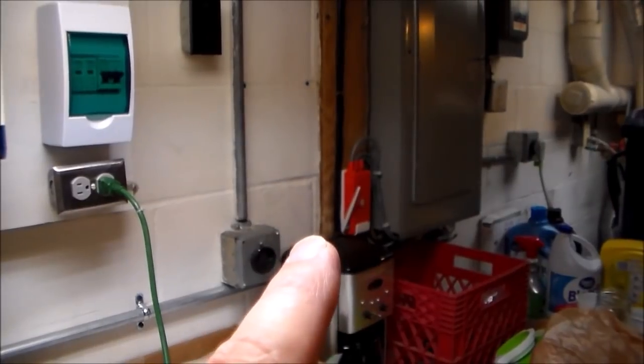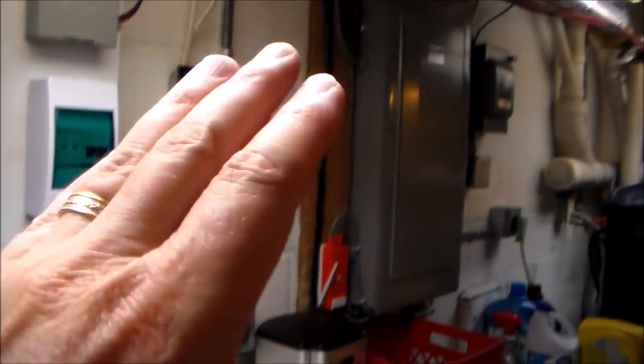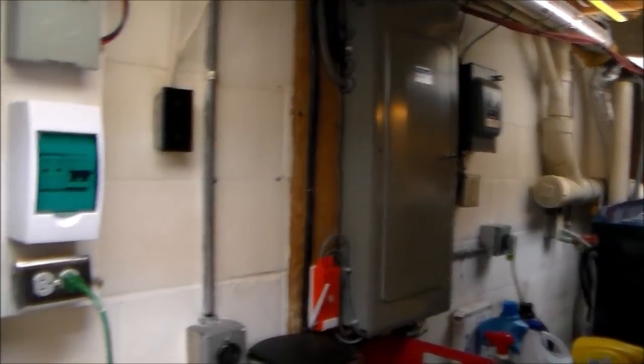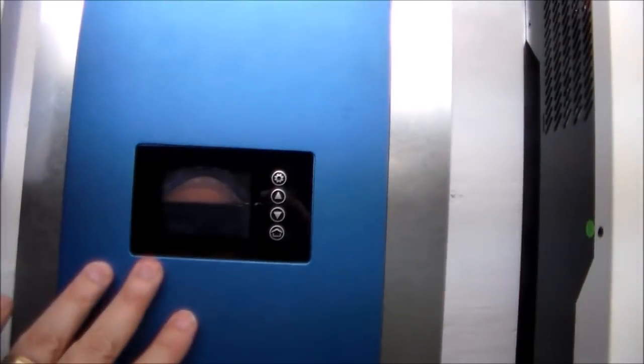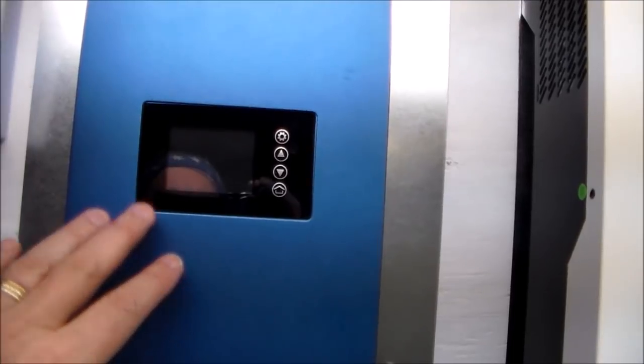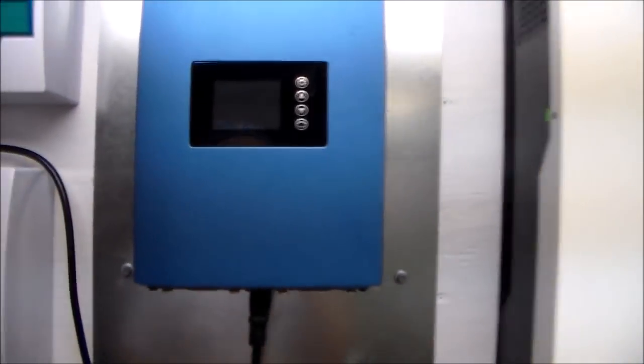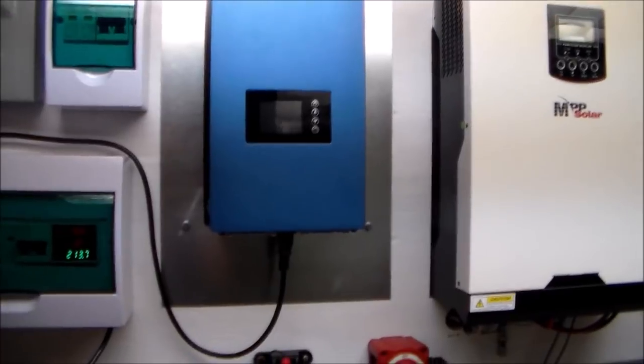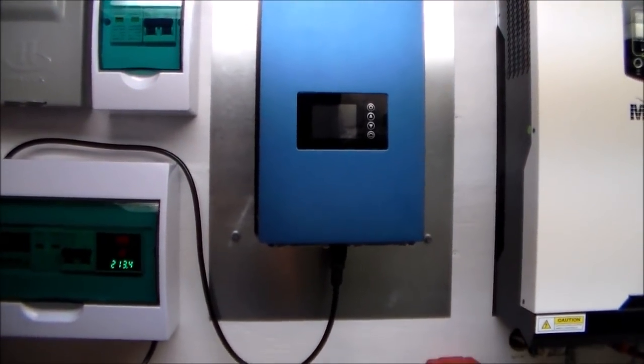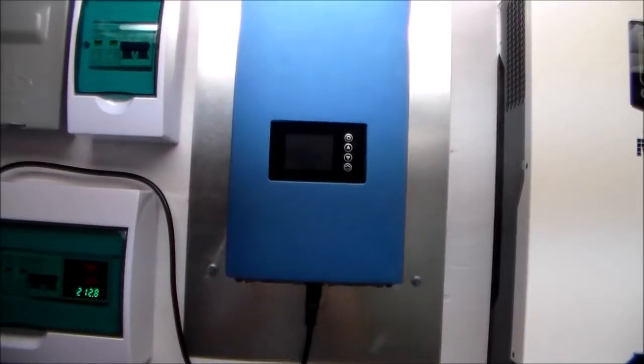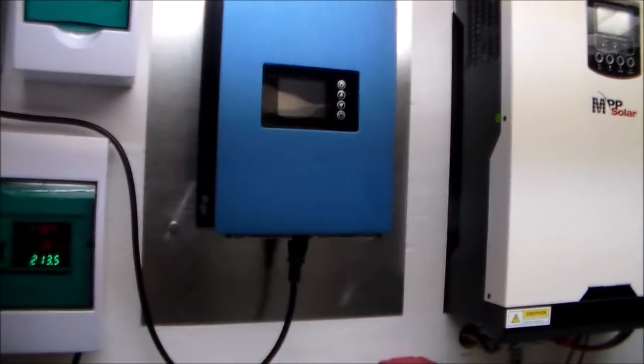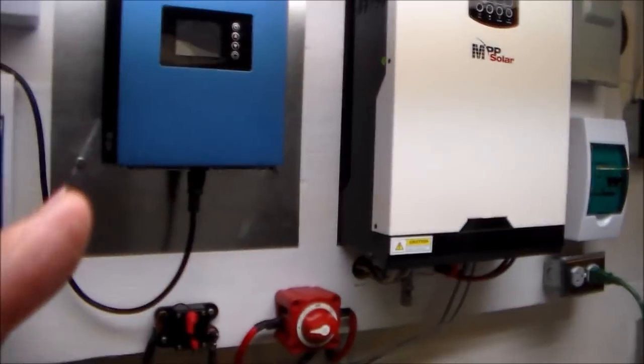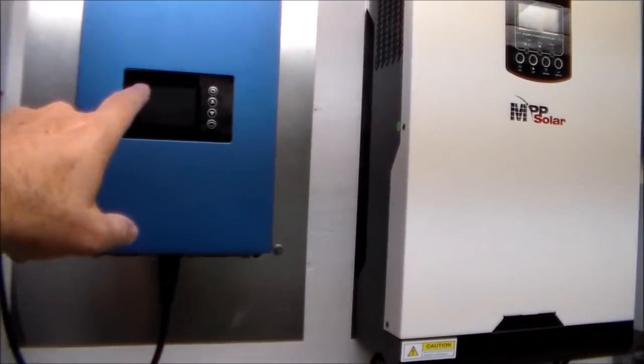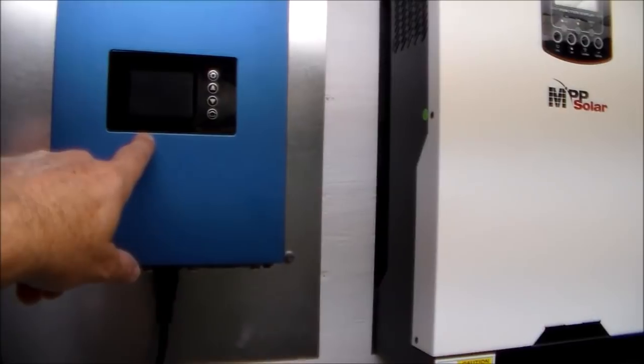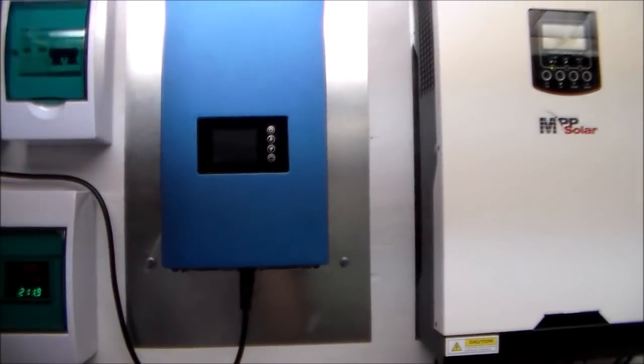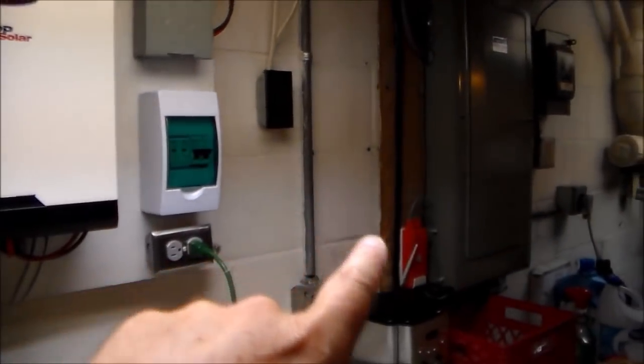The plan to troubleshoot will be to turn off all the breakers in my house except for the one this is running on, which is dedicated, so I know no other power is being used. Then I'll find and isolate one of my other outlets, plug in a light bulb, and measure it with my kilowatt meter so I know exactly how much that bulb is using. I'll compare that with what this shows as a load, and that should tell me if this is right or if that is right.